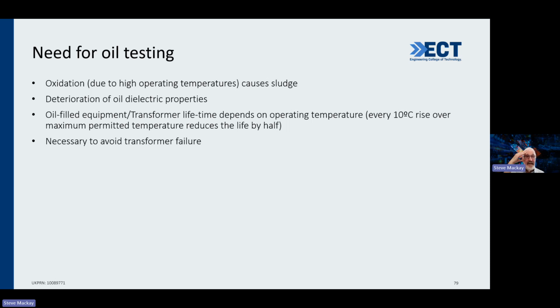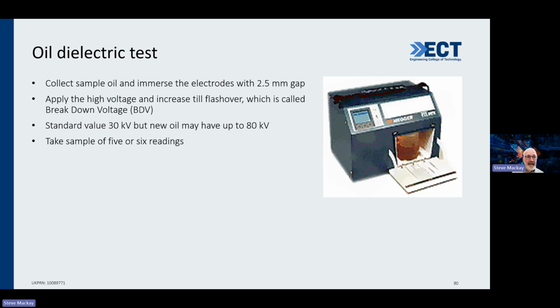And obviously there's a little suggestion here, which is not quite correct. Every 10-degree rise of maximum permitted temperature, you reduce your life by half. I don't know if that's quite correct, but it gives you a sort of indication. If the temperature is higher than it should be, you're probably reducing your transformer life. So it's quite important to watch out for things like that.